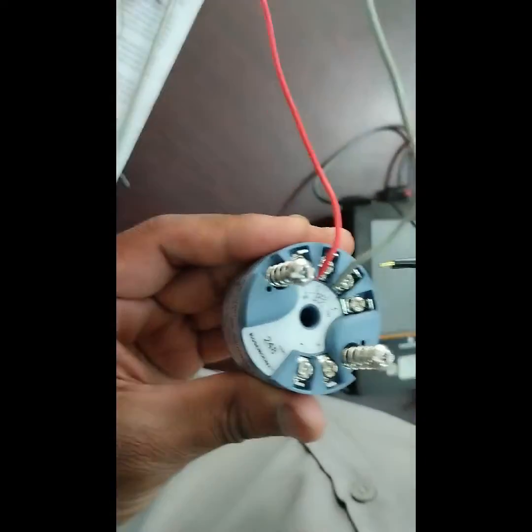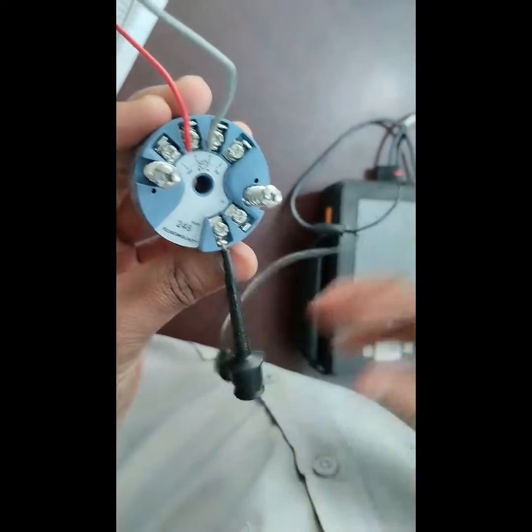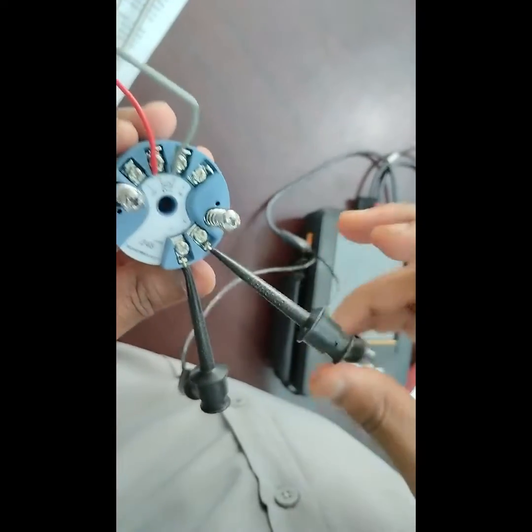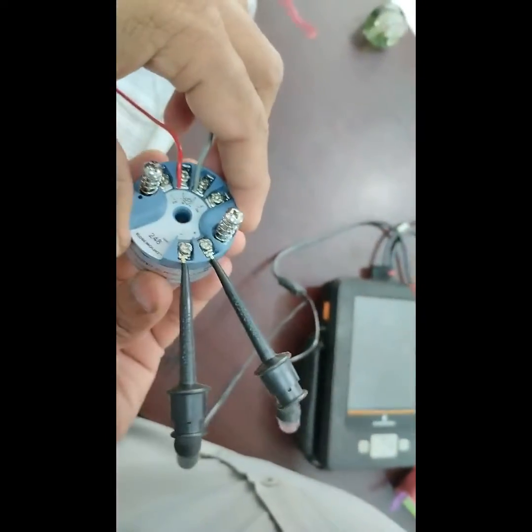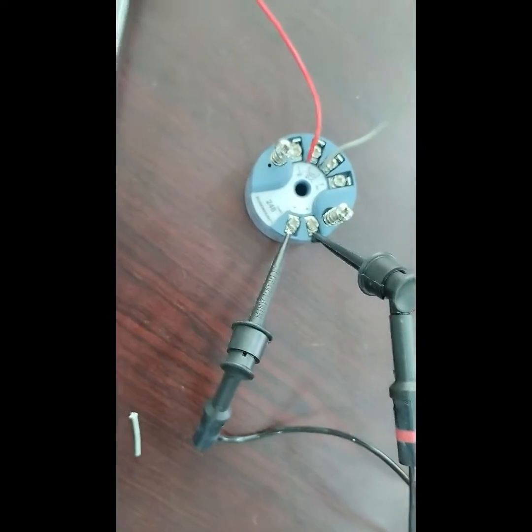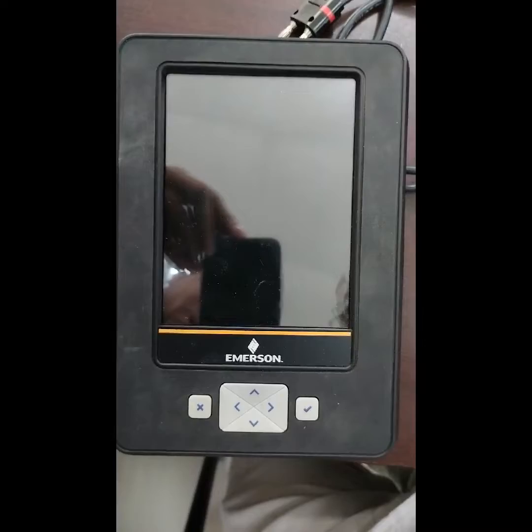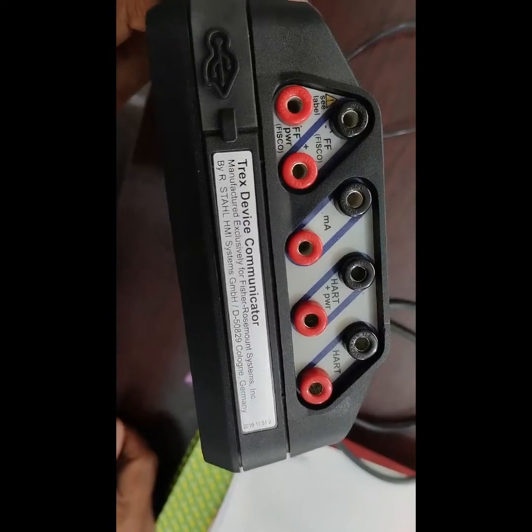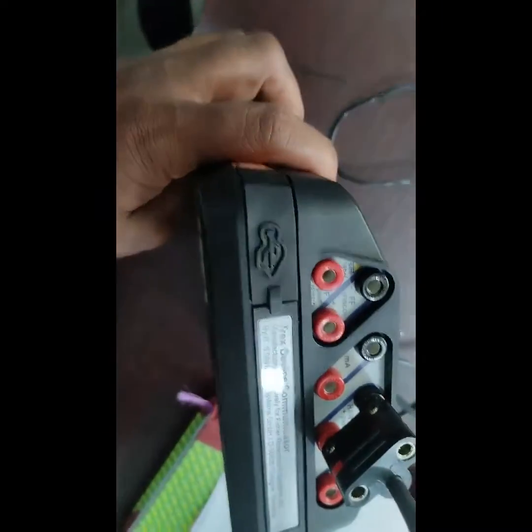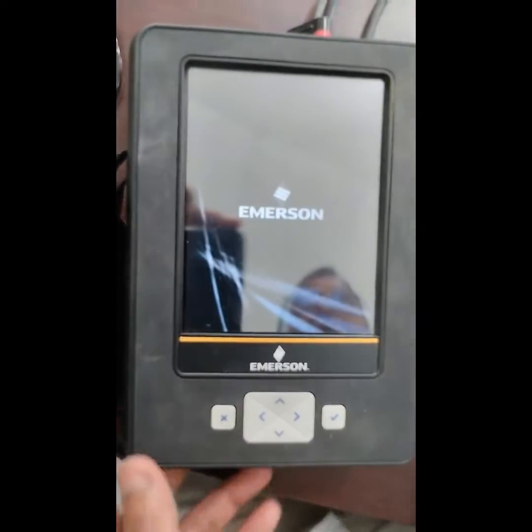Now I connect the Trex communicator with the transmitter. The plus terminal has to be connected to the plus terminal, and the minus terminal to the minus terminal. On the Trex side, we have to use power from the Trex. We use the HART plus power terminal — the HART plus power terminal. After connecting with the transmitter, we power on the Trex communicator.